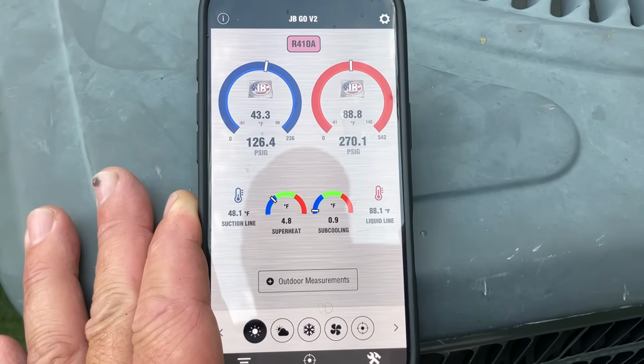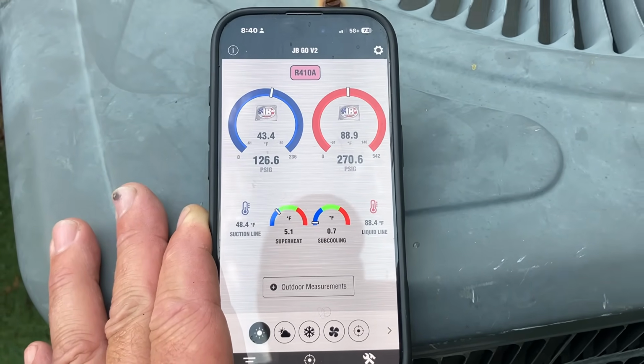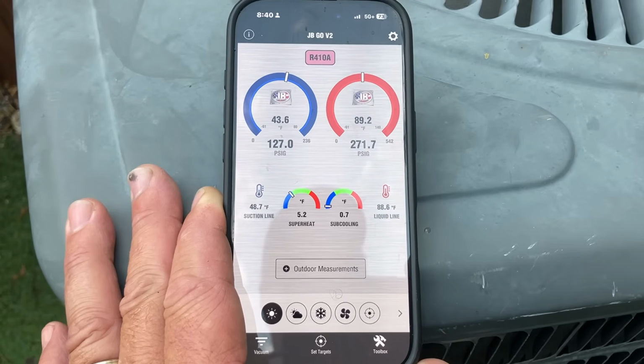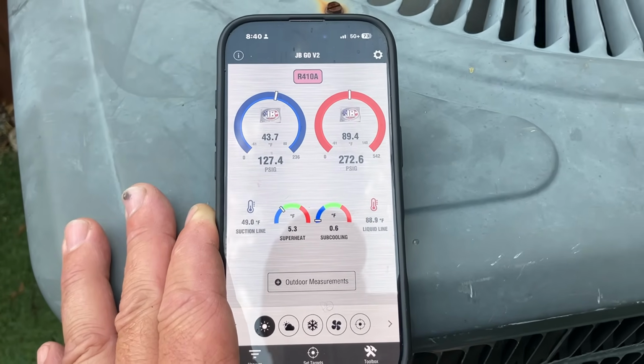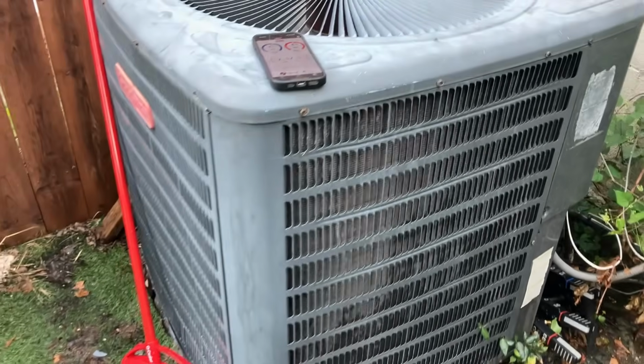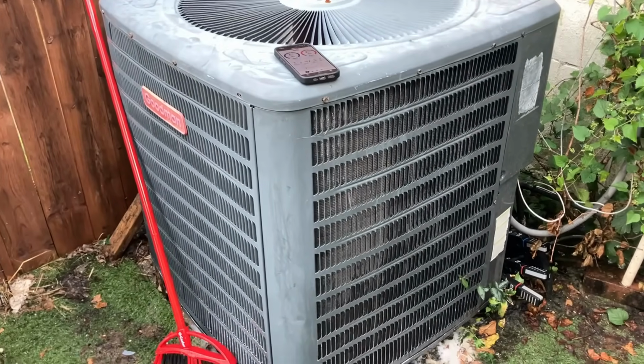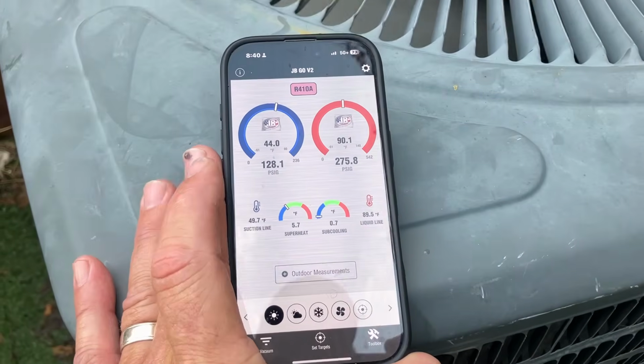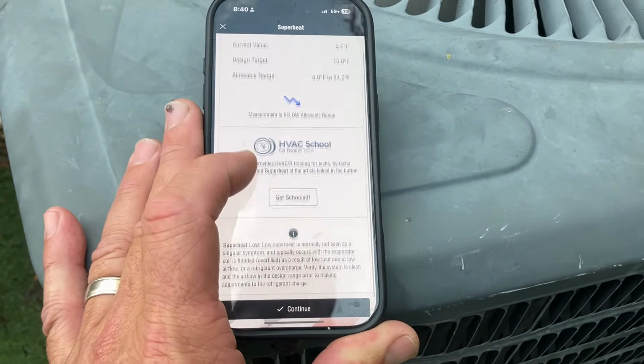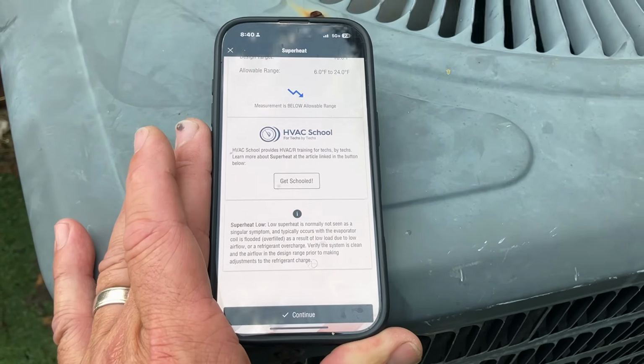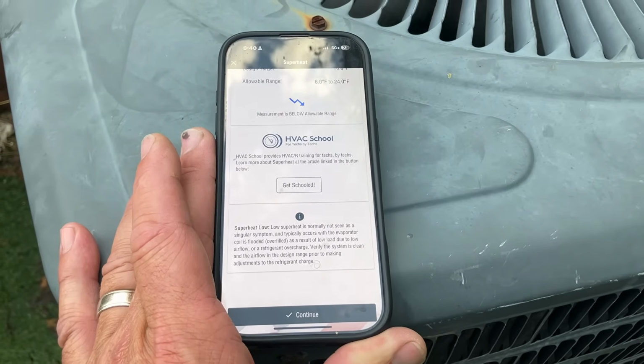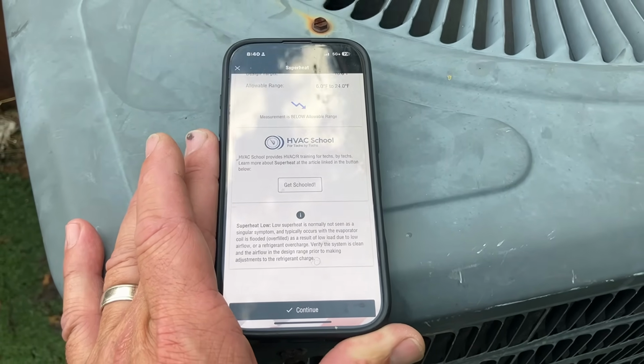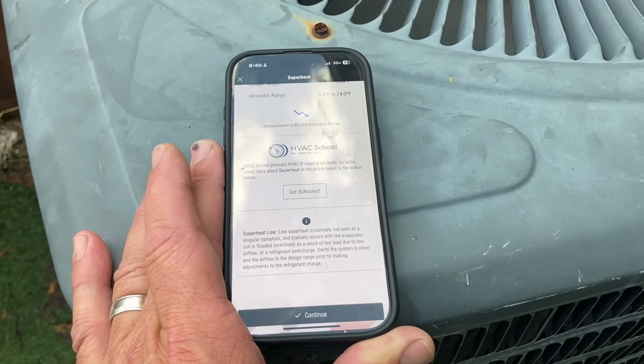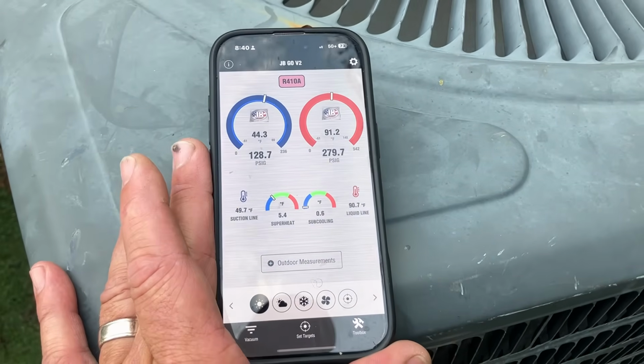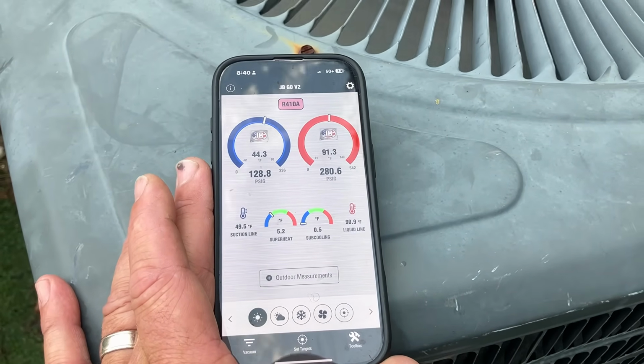All right, system's been running for a little bit. 126 and 270 are low in our pressures. A little over 5 degrees of superheat and barely just 1 degree of subcooling. Now, I did check up in the loft above the store. I didn't see a TXV, so we definitely have a fixed metering device there, an orifice. So we're going to be relying on superheat. And we are slightly low. We do have good airflow coming out of the diffusers. Our filter's clean and our fan motor's also good. We'll let this sit for a little bit longer.